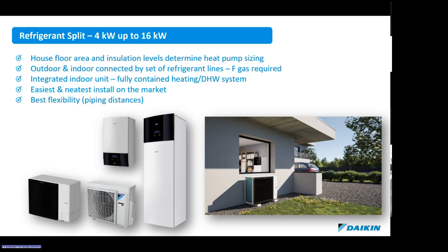Refrigerant split really means it's split in two, is the easy way of explaining. You will have an indoor unit and an outdoor unit, and the connection is made with refrigerant gas, generally R32. And the big advantage of that is the fact that it won't freeze. So a lot of county councils and housing bodies like the fact of refrigerant in it rather than water from outside to inside. If they have tenants in a property and the tenant leaves in November, and suddenly there's no power in the house because they were using pay-as-you-go meters or whatever, and then a really cold spell comes in before the new tenants come in March or something like that, the heat exchanger could freeze. So it's something that has to be very much taken into account. There are protections like antifreeze valves that can be used, but a lot of councils like the fact the system will never freeze because of the refrigerant in it.